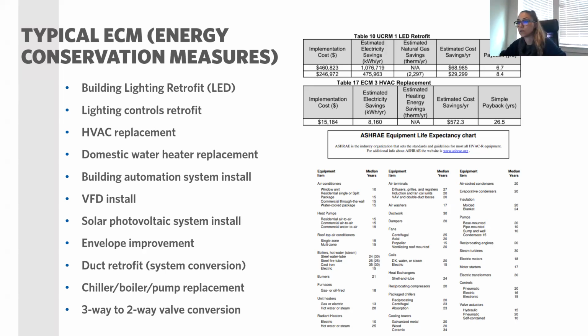Sometimes if it is a split unit, we just recommend an outdoor unit replacement. Or if they have already done some load reduction measures, like changing their windows or the lighting, the load in the building has changed, so sometimes we recommend downsizing the units as well. And obviously solar panels are really popular these days, so we recommend them. Envelope improvements typically take way longer periods. For lighting, we typically estimate 3 to 10 years, HVAC 7 to 25 years, renewable 15 to 25 years, and BAS 4 to 12 years. So these are typically our go-to ECMs.